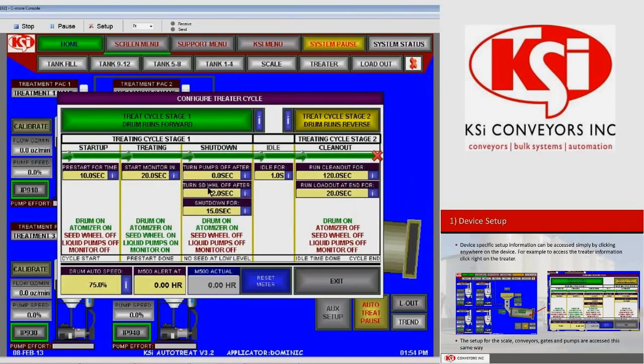Turn seed wheel off after. So again, we're going off of the low level. So once the low level no longer senses seed, we're going to let our seed wheel run for 2 more seconds. And then we're going to let the drum run for 15 more seconds in forward. After 15 seconds, the drum is going to turn off, and we're going to move to the next section here. You can see these arrows are telling you we're progressing this way.